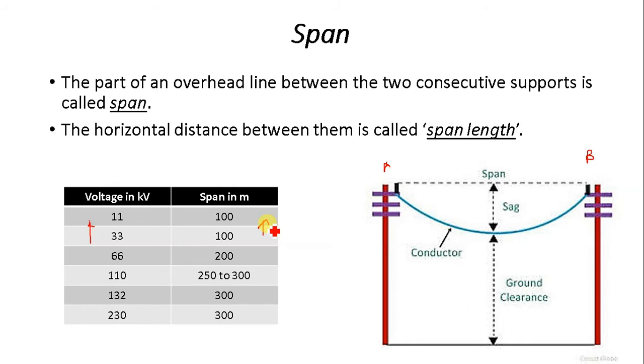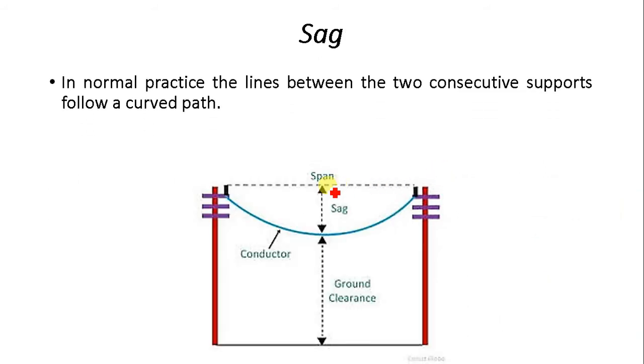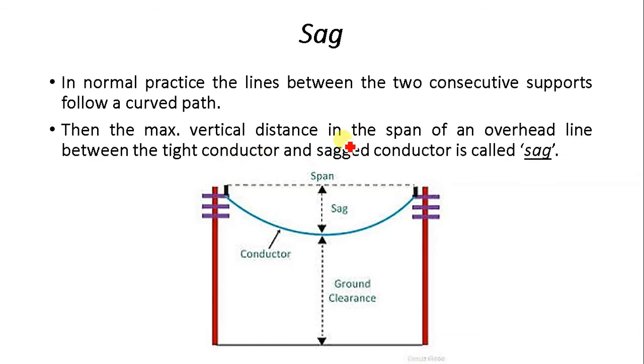Now before going to the second definition, when a conductor is placed, it will always have some kind of sag. When the conductor is placed in a straight line passing through the top points of the supports, it is called a tight conductor. But in normal practice, the line between two consecutive supports follows a curved path. The maximum vertical distance in the span of an overhead line between the tight conductor and the sag conductor is generally called sag.